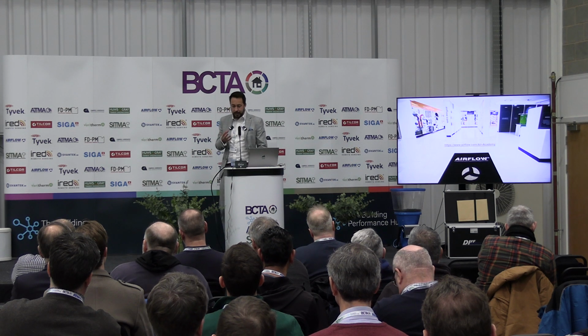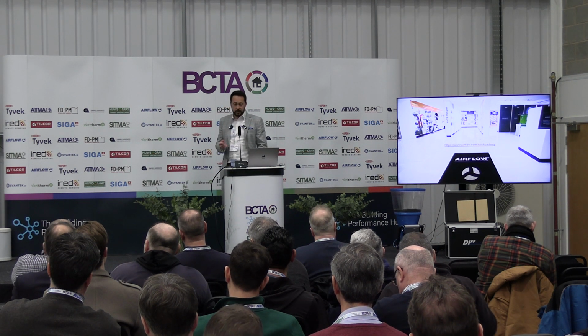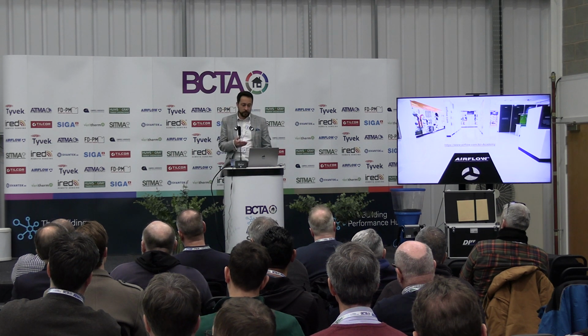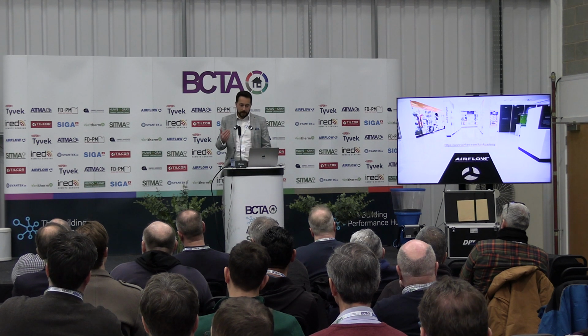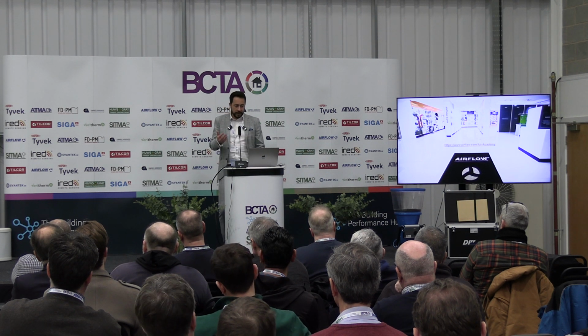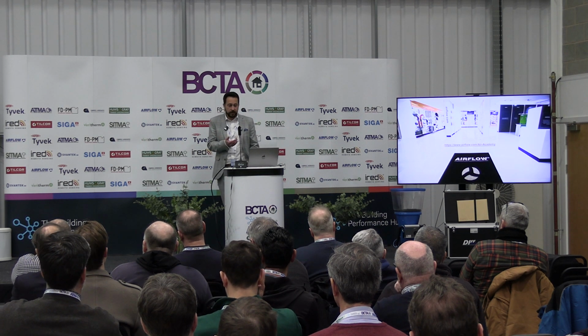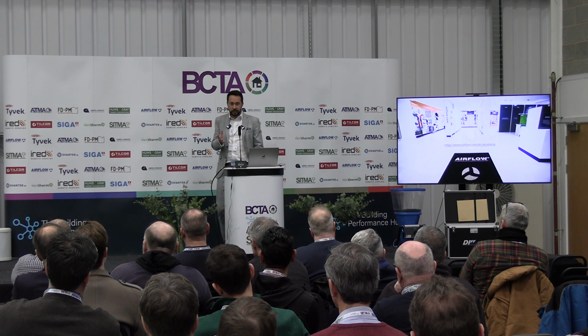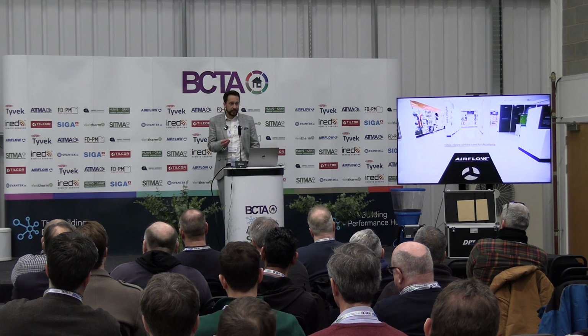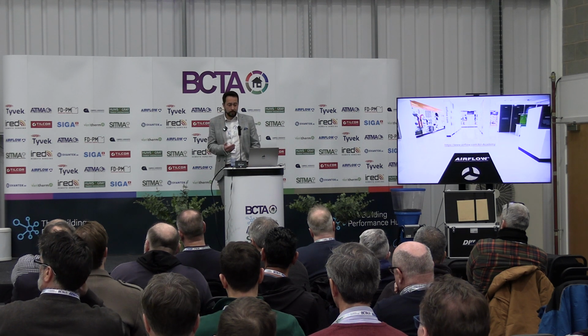So you don't necessarily need that air conditioning unit. You can just utilize the comfort heating or comfort cooling to top that air up to a more comfortable level. Nowadays, I think with the heat recovery systems, Airflow's units are up to 95% efficient on the heat recovery side. So the air coming off the heat exchanger in the wintertime, if we just took some examples of temperatures, if it was -5 outside and say 21 in the room, the air coming off those heat exchangers is still going to be around 18, 19 degrees. So then you only need to top up that air to a more comfortable temperature.